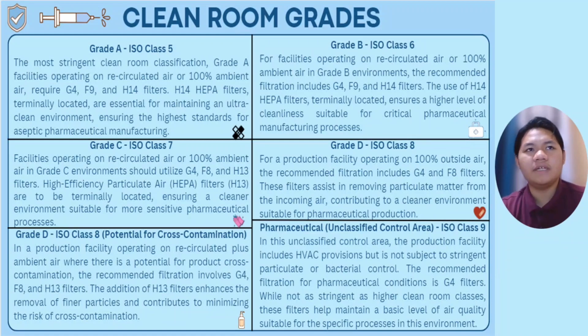For grade C, ISO class 7, the facility with recirculated or 100% ambient air also. The filtration is G4, F8, and H13 filters. The HEPA filters are terminally located. For grade D, ISO class 8, that is a production area with potential for cross-contamination. The filtration is G4, F8, and H13 filters for final particle removal. For grade D, ISO class 8, the production area using 100% outside air, the filtration is G4 and F8 filters for cleaner incoming air. And lastly, for the pharmaceutical unclassified control area, ISO class 9, the basic production area with HVAC, the filtration is G4 filters for basic air quality. That's all.